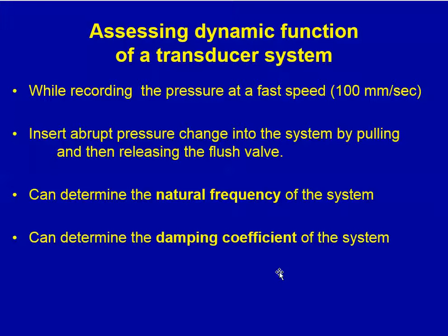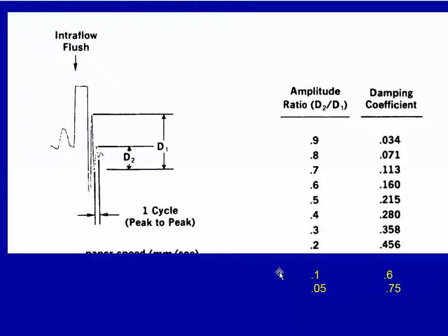The dynamic function of a transducer can be assessed — this is discussed in Miller's textbook. Basically, while recording the arterial trace, you insert an abrupt pressure change into the system by pulling and then releasing the flush valve. This results in a bouncing trace from which you can determine both the natural frequency and the damping coefficient.